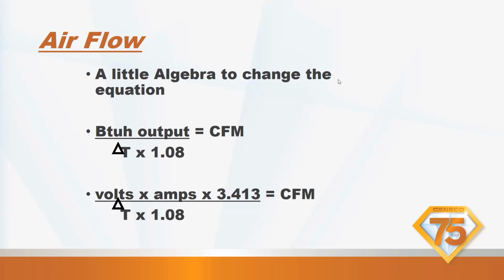Now, I know I'm going through this a little quickly, and you're not going to remember these. These are on the Gensco Tech form, the quick form for doing a job site. Okay, it's right up at the top left corner where the gauges are on the form. So you don't have to remember these. You just have to remember that these are available for you. With our equipment, our gas furnaces, if you look in the service facts, it's going to show you a chart that says BTUs by temperature rise. They've already done the math for you, put it into a chart in the service facts. So all you have to do is take your delta T, look at the delta T, go down to the CFM. It's pretty easy.